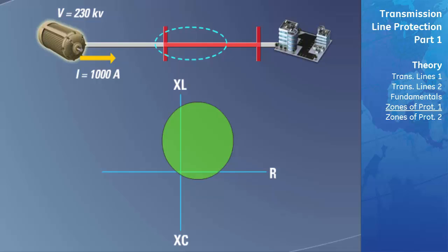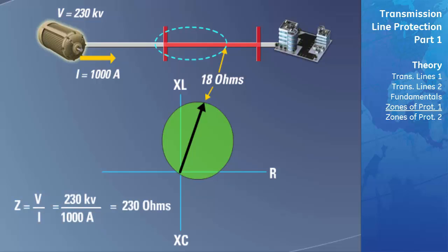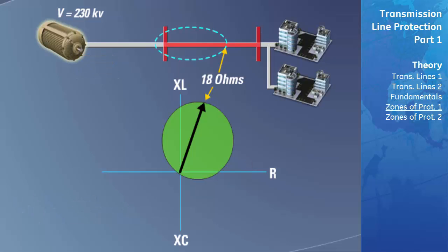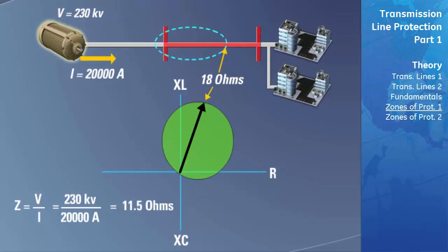For example, on the power system seen here, the reach of our Mho circle was programmed to be 18 ohms. Under normal circumstances where there are no faults on the power system, the impedance of the power system will be very large and the plotted measured impedance on the RX will be located close to the x-axis. If a substantial amount of load were now added to the power system, the current needed to feed the load would increase substantially. Even though there is no fault on the transmission line, the newly calculated impedance of the line would be less than the reach of the Mho circle zone. However, since the load that was added is mostly resistive, the plotted impedance point would be much closer to the origin but still very close to the x-axis. Since the Mho circle is positioned where it is on the graph, there is very little area included in the zone of protection in the resistance direction. Therefore, the new impedance will not fall into its zone of protection and the relay will not trip.